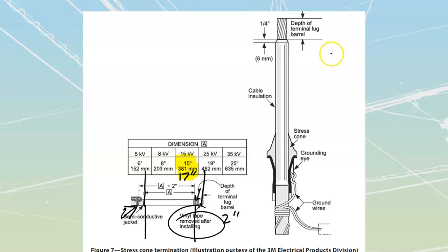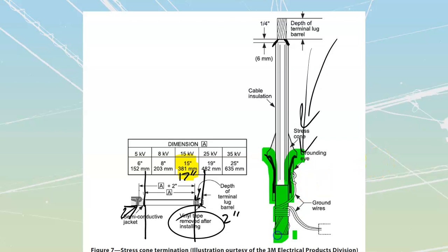Once I've got all of that, I'm going to follow the installation instructions. There's usually some grease and stuff like that, you lube this thing up. You're going to pencil this, meaning cut it on an angle, so we get a gradual entry onto these things. We do the penciling because it also avoids corona problems. We pencil that, then slide this thing all the way down to the bottom, making sure the inside section highlighted in green, which is grounded, overlaps my actual semicon. Then there's an eyelet I'll attach at least one of my ground wires to, because that eyelet is also attached to the internal semicon inside here.